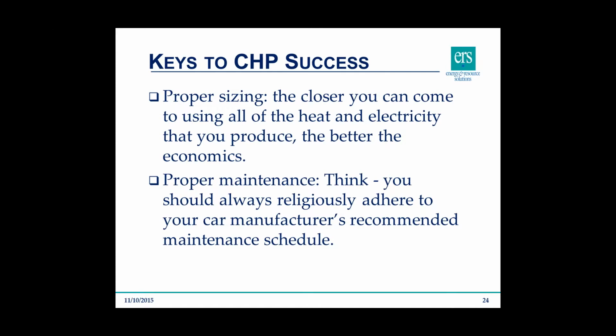The keys to CHP success: you want to make sure that system is sized well. The closer you can come to using all of the heat and electrical output of a CHP system, the better the economics. Typically, we see systems that are successful having a minimum runtime of 6,000 hours per year. To translate into day-to-day thinking, your CHP system should run full bore about 16 to 16 and a half hours a day at minimum to have a successful installation.